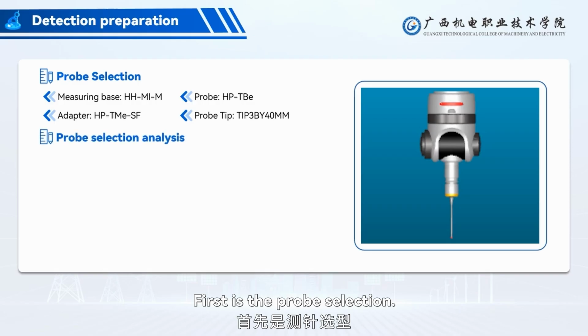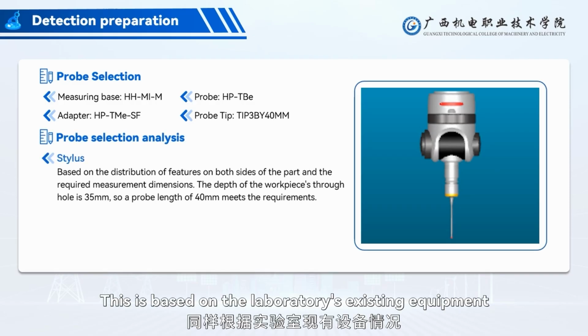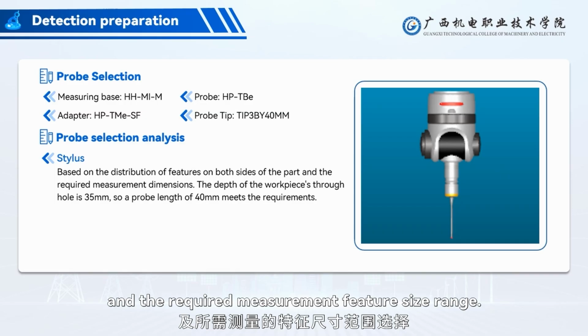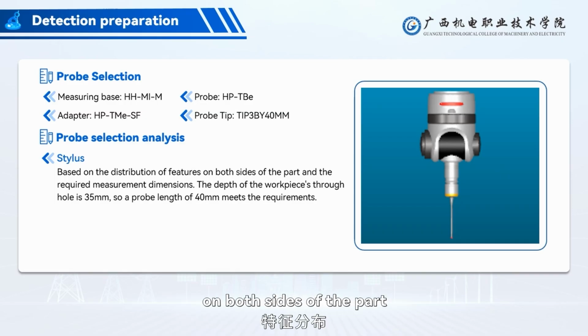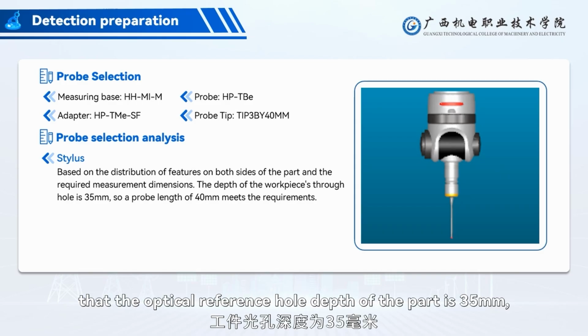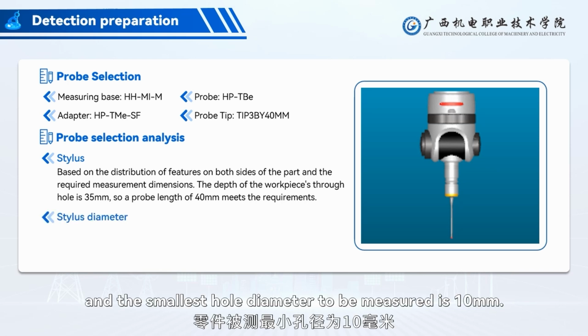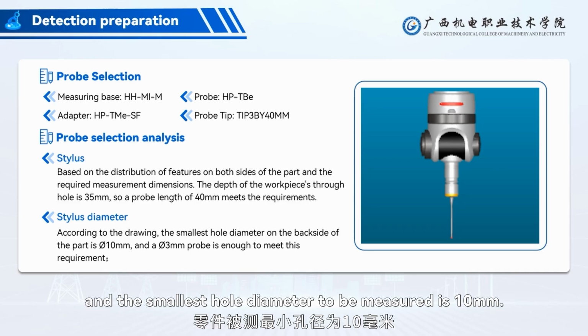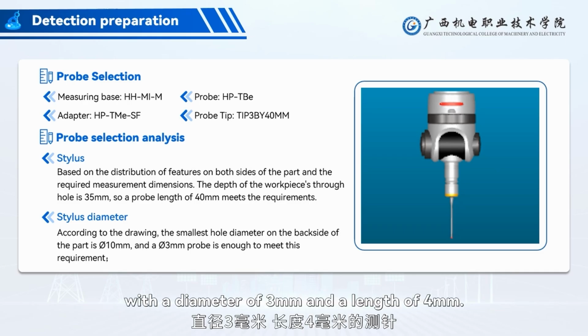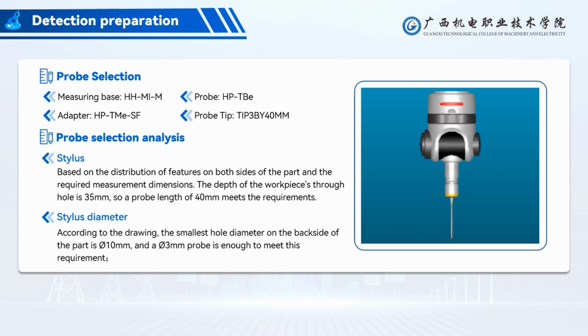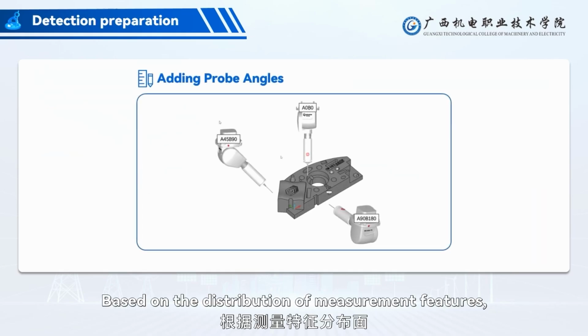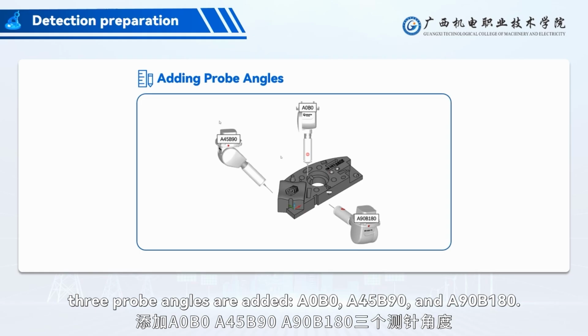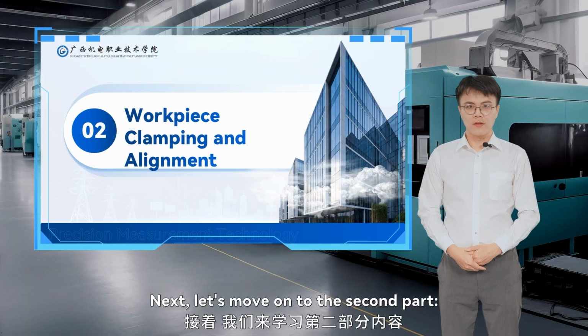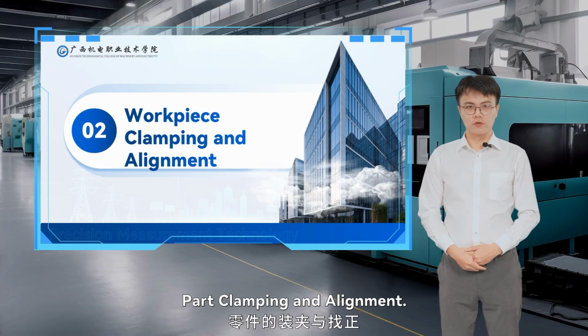First is the probe selection. This is based on the laboratory's existing equipment and the required measurement feature size range. Here, based on the distribution of features on both sides of the part and the required measurement range, we know from the drawing that the through hole depth of the part is 35 mm, and the smallest hole diameter to be measured is 10 mm. Therefore, we choose a probe with a diameter of 3 mm and a length of 40 mm. Based on the distribution of measurement features, 3 probe angles are added: A0B0, A45B90, and A90B180.